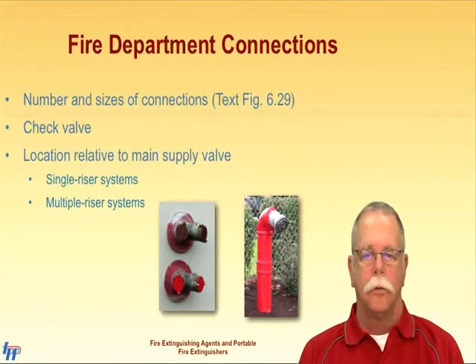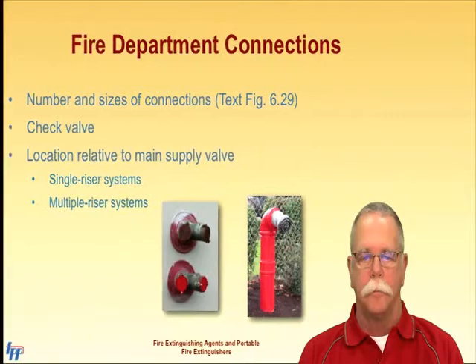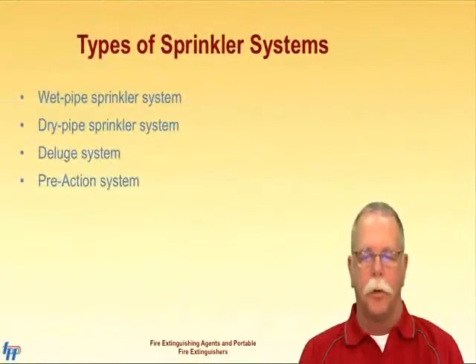On a single riser system, the FDC admits water to the system on the riser side of the main supply valve. This is done so that the interruption of a municipal water supply does not affect the fire sprinkler operation. If the system is a multiple riser system, water is introduced between the main supply valve and any floor or zone control valves. This is done so that the water can be distributed throughout the system even if one floor or zone has been shut down.